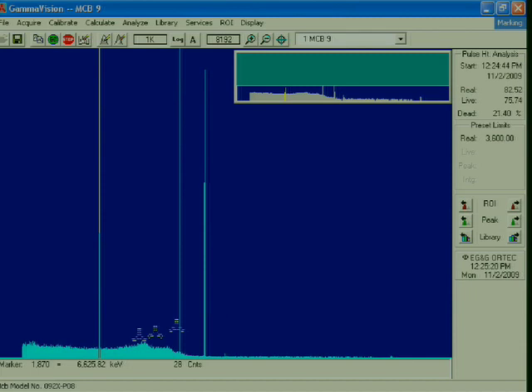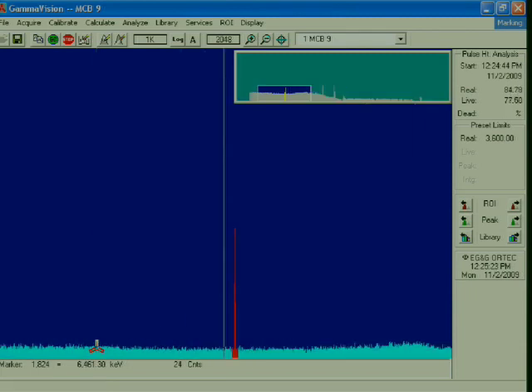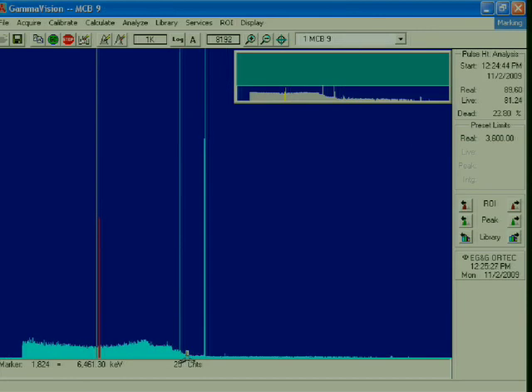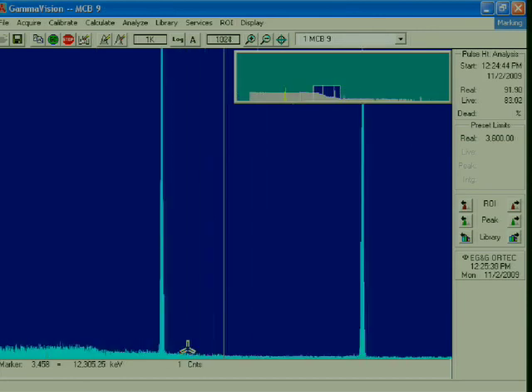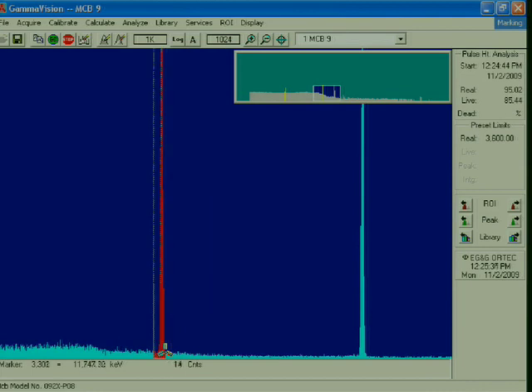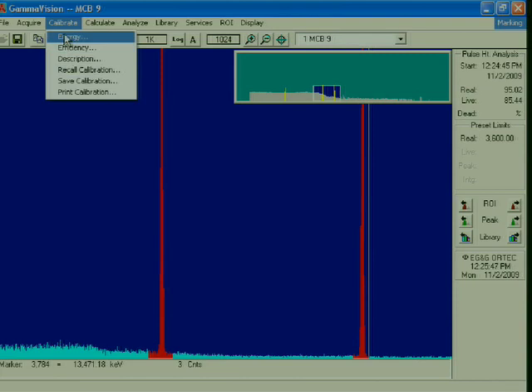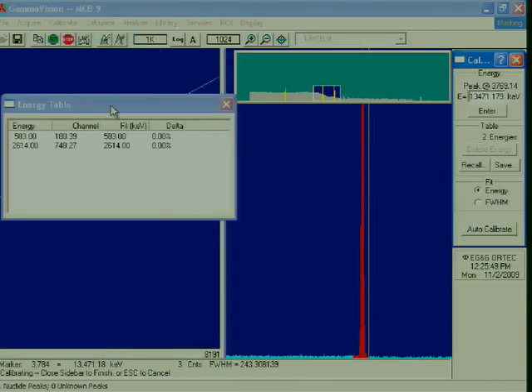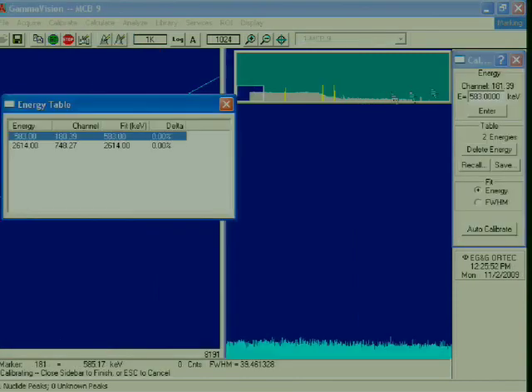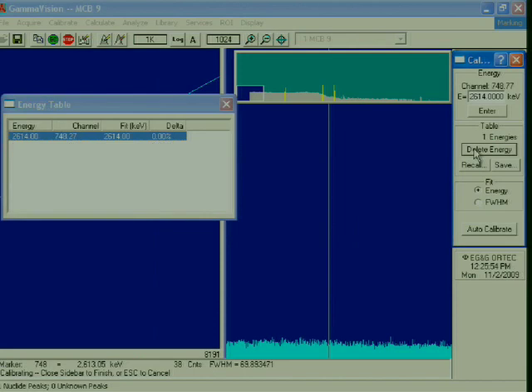So if I go back for a minute. Okay, so there's the cesium. We'll do this for the cobalt. Okay, so now I've got my 3 peaks, and I go up here and I say calibrate the energy. It has some calibration in its memory. We'll tell it to forget about that.